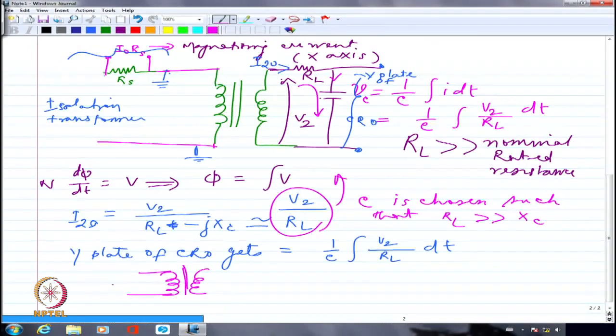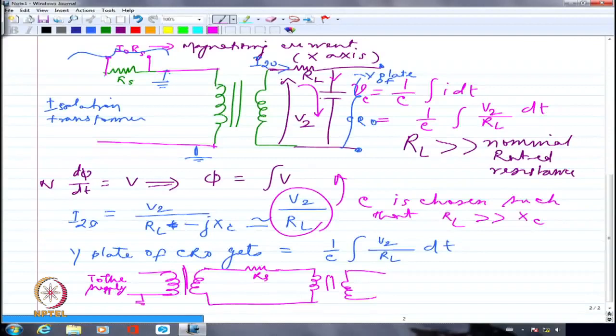So I know for sure that probably this side is grounded. It doesn't matter. From here I will connect it to RS and whatever I have to do, and then I will connect it to this transformer. So this is the transformer under test, whereas this transformer will be the isolation transformer. Got it? So now, after all, the transformer under test and the transformer which is connected to the other side, in terms of electrically, they are not connected together.